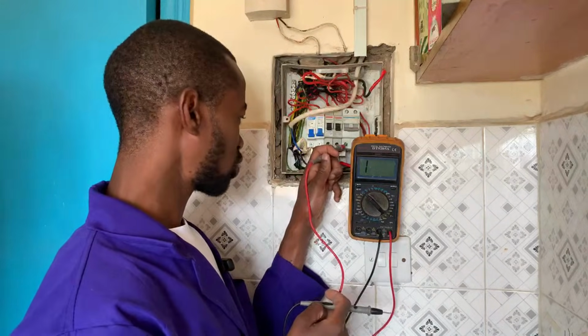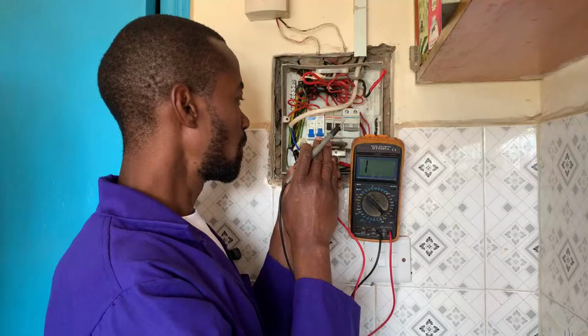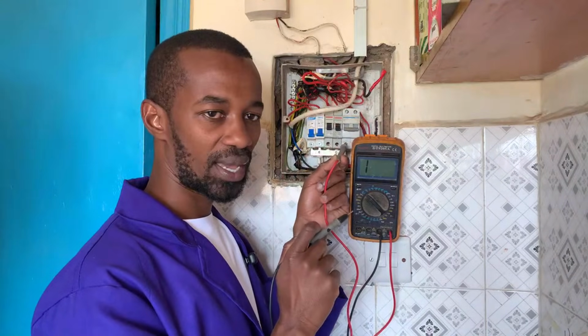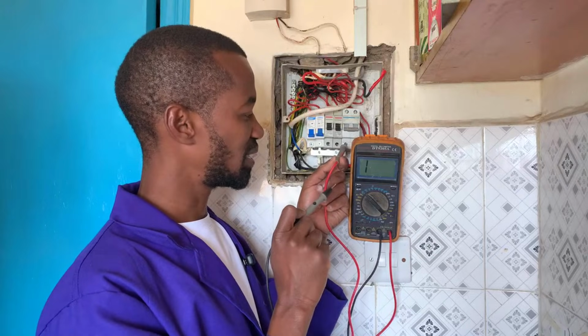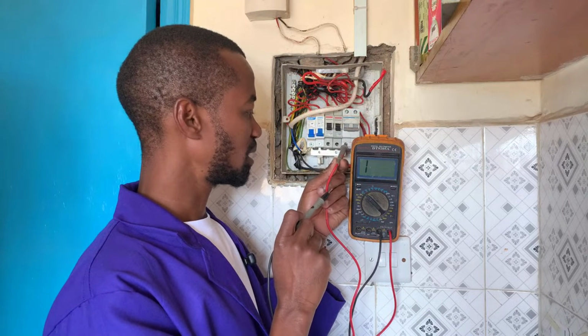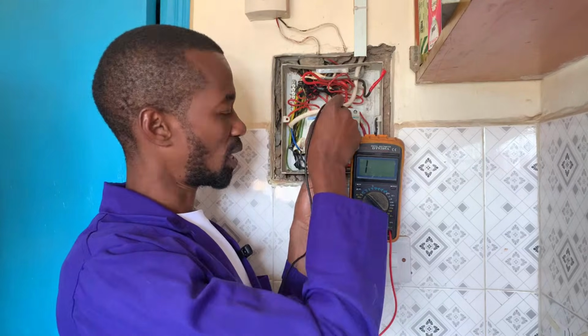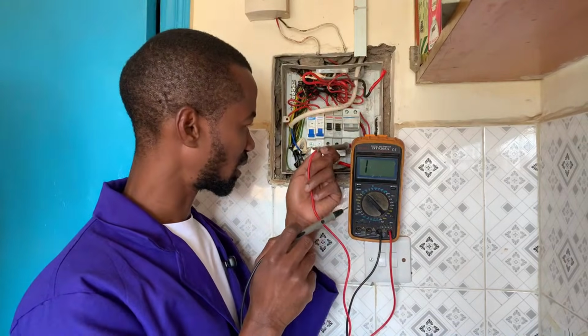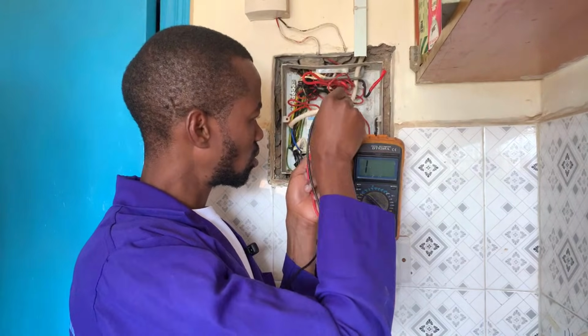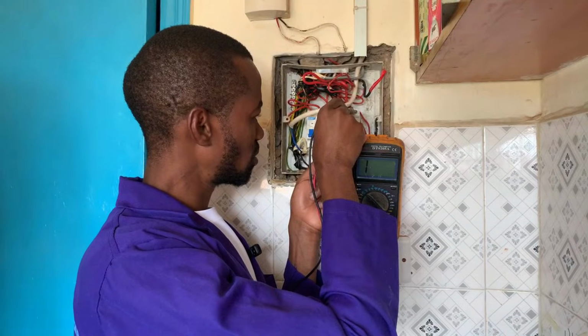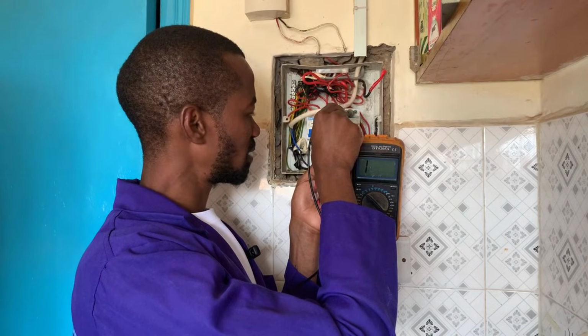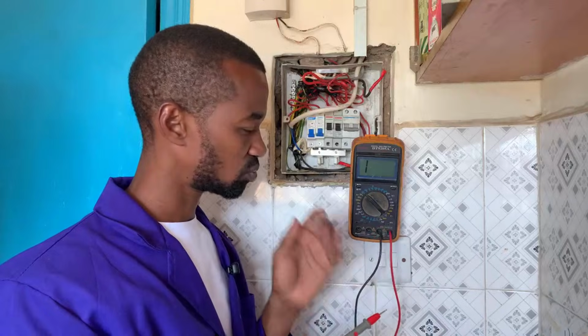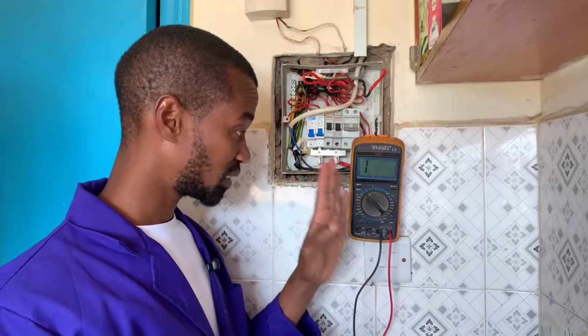So between the output and the input at the point where the double pole MCB is switched off, we get a 1, meaning it is not allowing current to flow. Another thing is on the neutral - on the output and the input of the neutral, as well as the line, we get a 1.